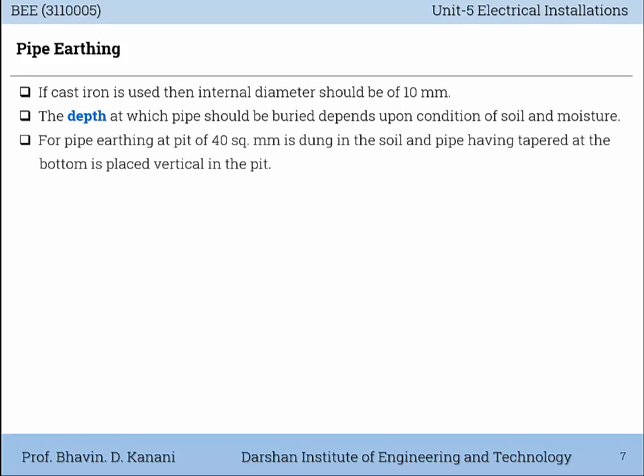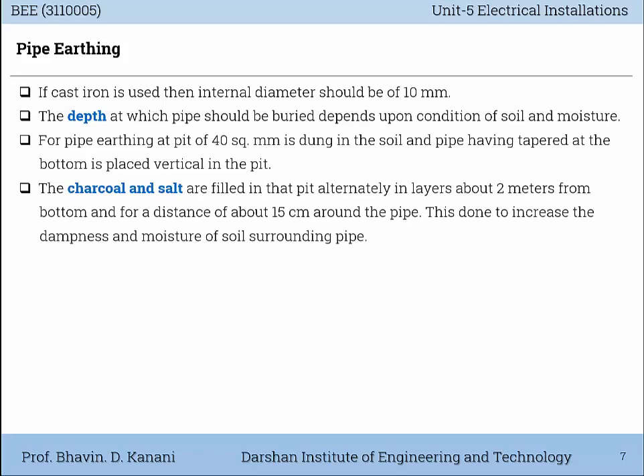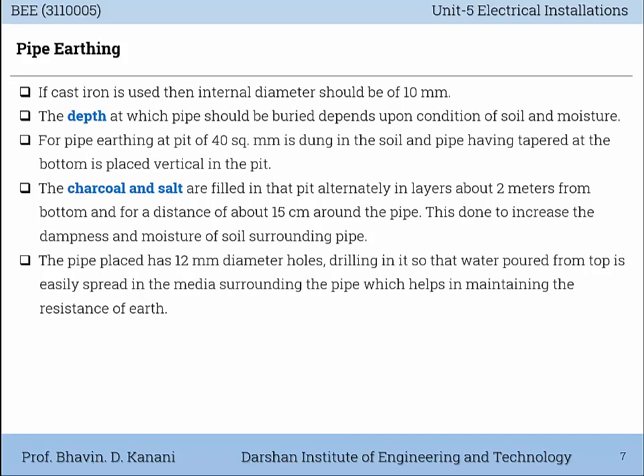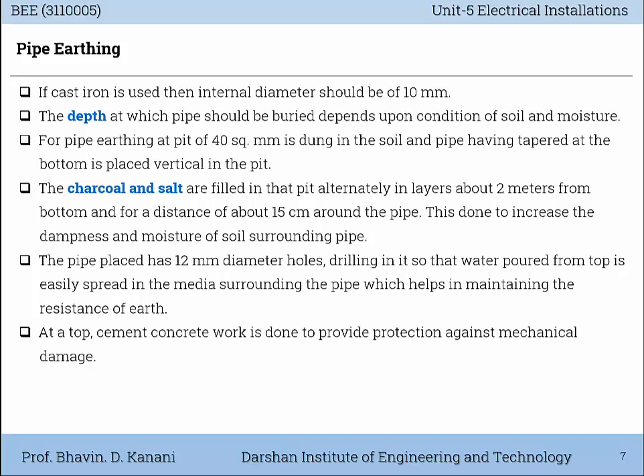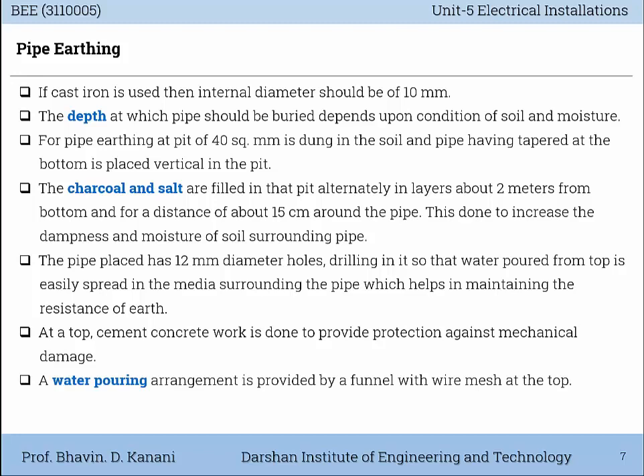For pipe earthing, a pit of 40 square mm is dug in the soil and a pipe tapered at the bottom is placed vertically in the pit. Charcoal and salt are filled in that pit alternately in layers, about 2 meters from the bottom and for a distance of about 15 cm around the pipe. This is done to increase the dampness and moisture of the soil surrounding the pipe. The pipe has 12 mm diameter holes drilled in it so that water poured from the top easily spreads in the media surrounding the pipe, which helps in maintaining the resistance of earth. At the top, cement concrete work is done to provide protection against mechanical damage. A water pouring arrangement is provided by a funnel with wire mesh at the top.